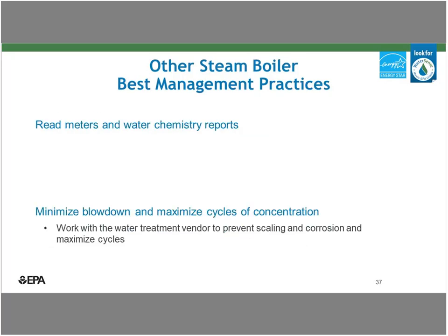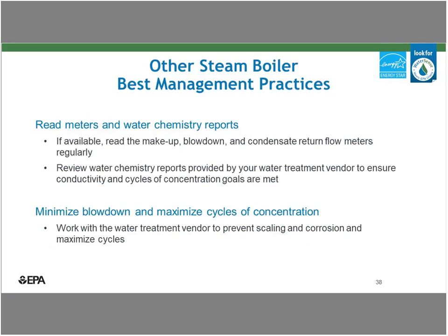Some other concepts that we presented earlier for cooling towers also apply to steam boilers. Install and read makeup and blowdown meters. Maximize the cycles of concentration by capturing as much steam condensate as possible and minimizing your blowdown. And again, work with a treatment vendor that specializes in water efficiency to maximize the cycles while still preventing scale and corrosion. This should reduce your water use, reduce your chemical use, and general overall operating costs.